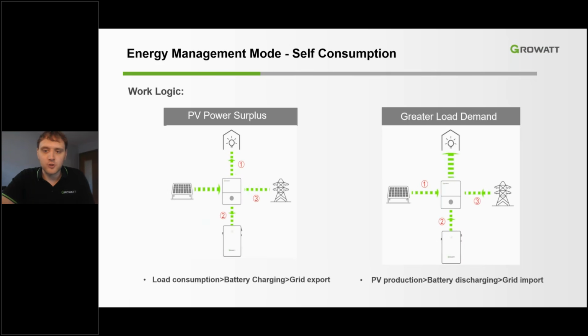Battery charging occurs when the load demand is met by the solar production, and exportation to the grid begins only after the loads have been powered. During the night, consumption is handled by the battery first, and energy is only imported from the grid once the state of charge of the battery reaches a critical level. And that critical level can be set by the user as well.